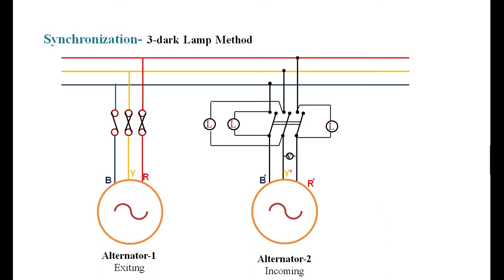The second condition to fulfill is frequency — the frequency of the incoming machine must match the bus bar frequency. The third important condition is phase sequence — the phase sequence of the incoming machine must be the same as the bus bar phase sequence. To judge this, just build up a small voltage and observe the lamps: if all the lamps are flickering — going dark and bright simultaneously — you can conclude that the incoming machine has the same phase sequence.